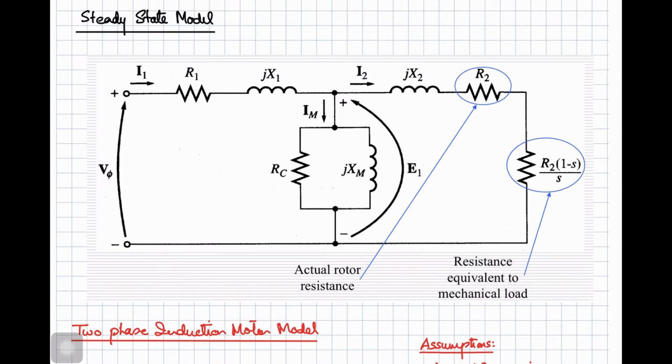Stator frequency variation is there in applications, for example, variable speed drives, because you change the speed of the induction motor by changing the frequency, that is by changing the synchronous speed, which is given as 120 F by P. So the variable speed drives are converter fed from finite sources. You use inverter circuits along with the sources to provide power to your induction motor at required voltage and at required frequency.